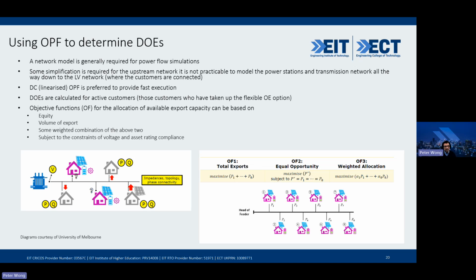So you can also use an objective function to maximize the volume of export. In this case, everybody will get a different limit, and probably the one closest to the distribution substation transformer will be given a bigger limit compared with the one at the end. So it could be allocated on that basis, or it could be a combination of both, looking at equity and also volume of export.